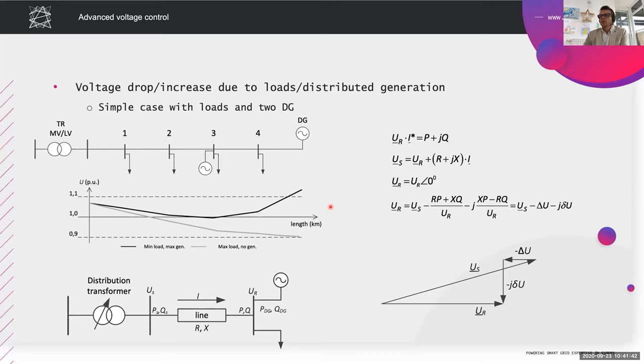As you may know, the voltage limits, as indicated here in this voltage graph, according to the power quality standard which is used in Europe, are set to 10% above the nominal value and 10% below the nominal value. So the voltages for the users at the user connection point should be between these two limits. Otherwise, the devices we are connecting to the network may have problems. And usually in the case of distributed generation, if the voltage gets above 10% above the nominal value, so above 110%, then the distributed generator is disconnected.